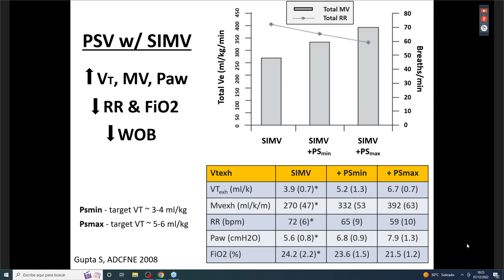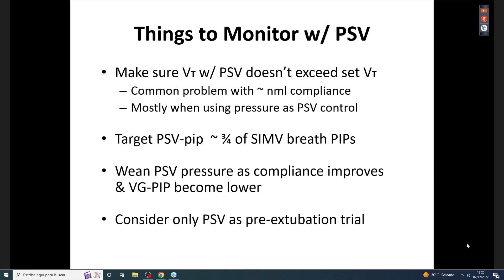Now, there are a variety of things you have to keep in mind when you're using pressure support. One of the things I see most commonly is that people may set a pressure support limit that is high and tends to create pressure support breaths that are often higher than the set tidal volume breaths that you're trying to achieve. So pay attention to where your pressure support is. I tend to target a PIP that's about 3/4 of the ventilator breath PIPs in order to not exceed set tidal volumes. But it's an adjustment that needs to be monitored closely in order to make sure you don't provide excessive tidal volume breaths as lung compliance improves with your pressure support breaths.